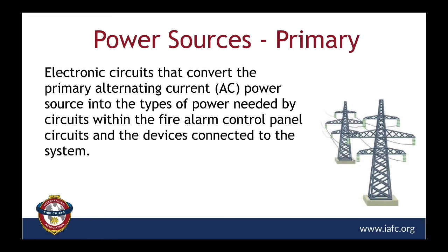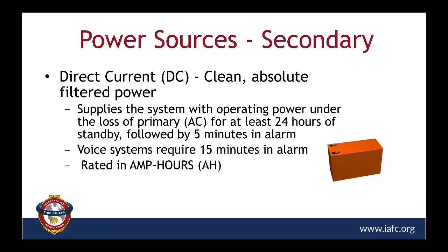So, if you stop and think about it, fire alarm systems have to perform during normal conditions and also during emergency situations. For this reason, fire alarm systems are required to have at least two independent and reliable electrical power sources. Now, the primary power is usually supplied by the 120 volt AC that is supplied by the electric utility company. And then this voltage is transformed or stepped down to a lower 12 or 24 volt DC that actually operates all of the system input, output devices and controls. Next slide.